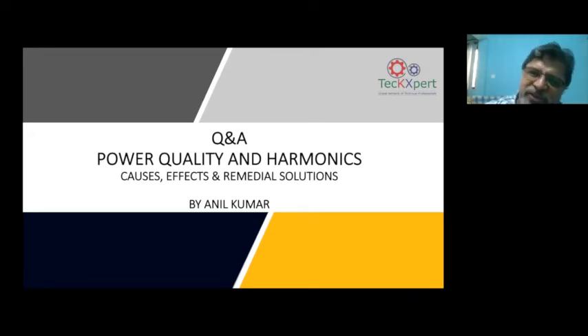An active harmonic filter is the solution to avoid all such problems, because an active harmonic filter can filter the second to the 50th harmonic in one go. Not all active harmonic filters do even harmonics. You rightly said that. That is why you have to go with the right manufacturers.